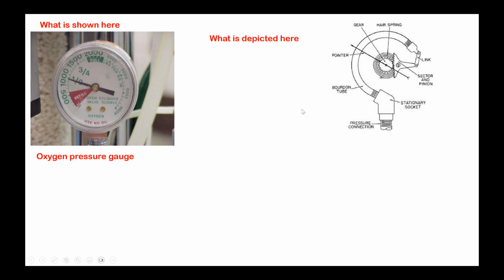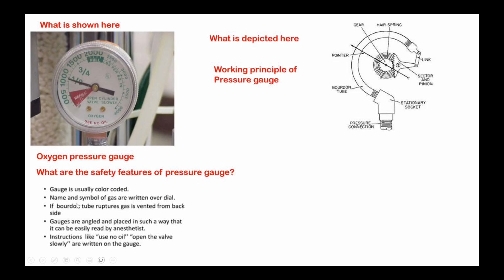This is the Bourdon gauge working principle. What are the safety features in the pressure gauge? That is another common question. It is color coded. The name and symbol of the gas is written over the dial. If the Bourdon tube ruptures, gas is vented from the back side, not the front side, to protect the anesthetist. Gauges are angled and placed so they can be easily read by the anesthetist. Instructions like 'use no oil' and 'open valve slowly' are written on the gauge.